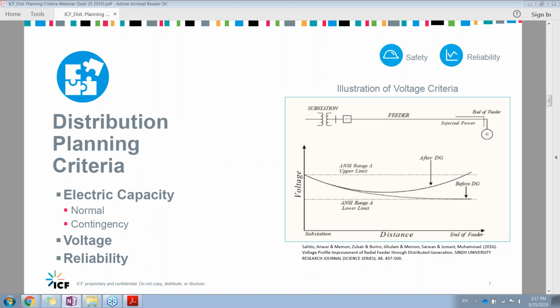Those thermal limits are typically calculated based on industry standards, but there are assumptions built in—for example, the ambient air temperature, or for an overhead line, the wind speed available to dissipate that heat.